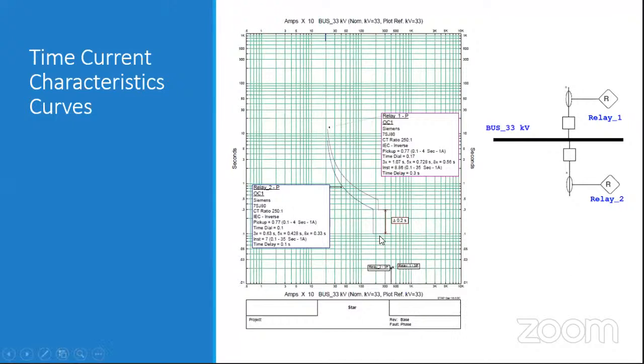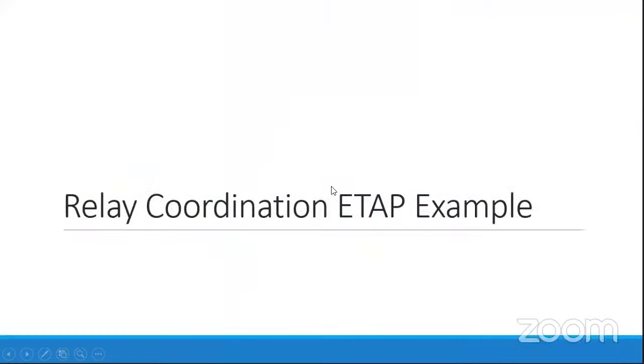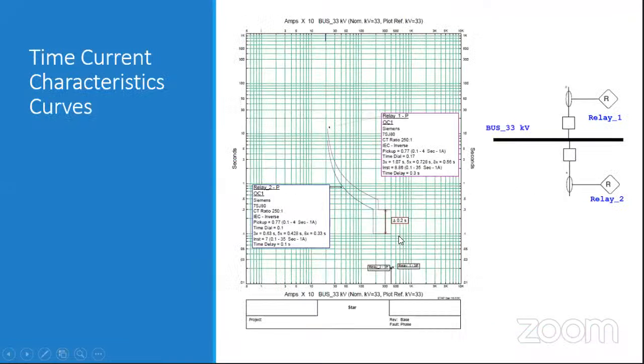So the time margin you can see in this plot, the time margin that has been given is 0.2 seconds between these two curves. This guideline is also given in IEEE standard 242, used for relay coordination, the IEEE Buff Book, recommended practice for protection and coordination of industrial and commercial power systems, where it is also defined.